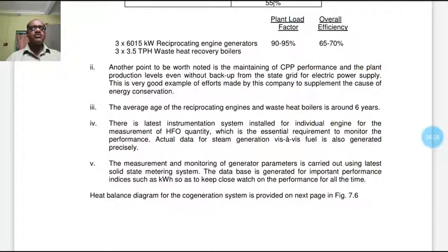There is a instrument system installed for individual engines for the measurement of HFO quantity, which is an essential requirement to monitor the performance. Actual data of steam generation via fuel is also generated precisely. The measurement and monitoring of generator parameters is carried out using the latest solid state metering system. The database is generated for important performance indicators such as kilowatt hour, so as to keep close watch on the performance all the time.